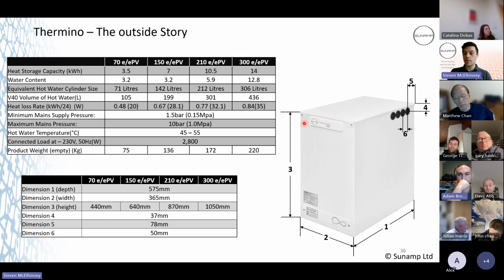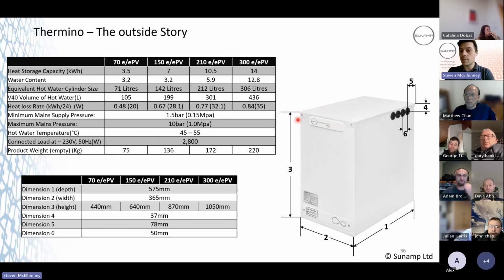So again, bear in mind, if you're thinking about putting this in a cupboard and there's fixed shelves above the unit, we need a 450mm clearance above that, because this lid pulls forward and lifts up, and then you can lift the lid off, but you still need a little bit of workability just to do your wiring inside the unit as well when you're commissioning it. So just bear that in mind.